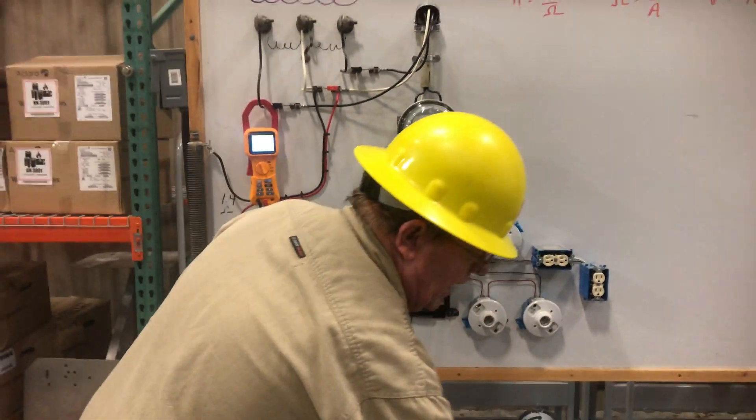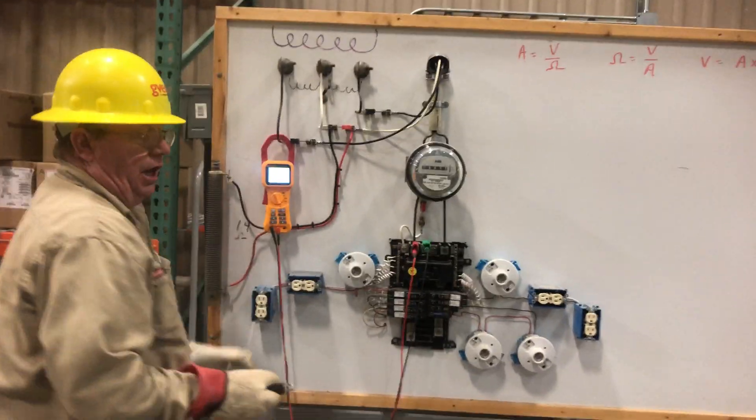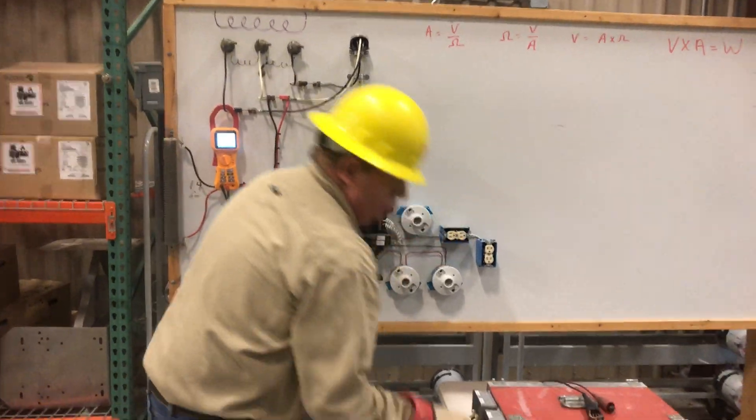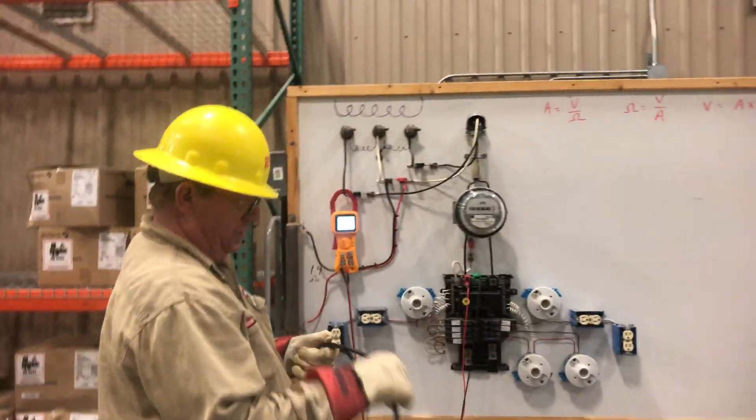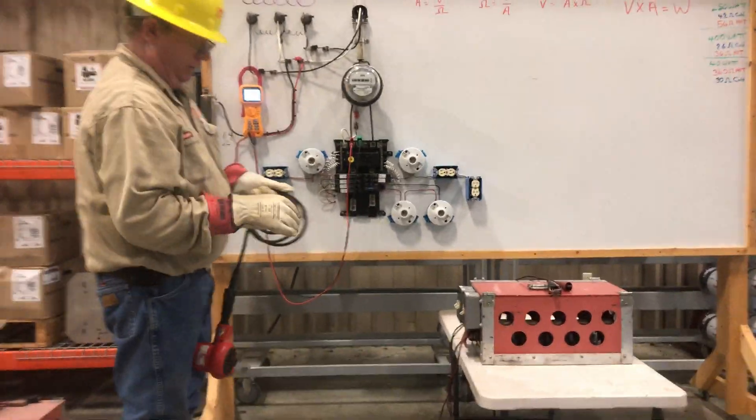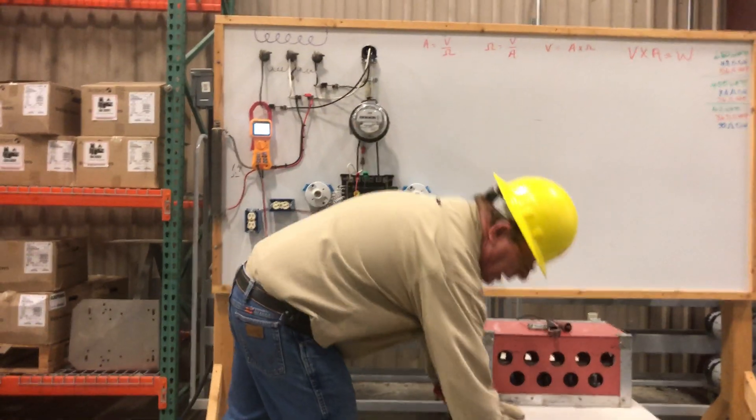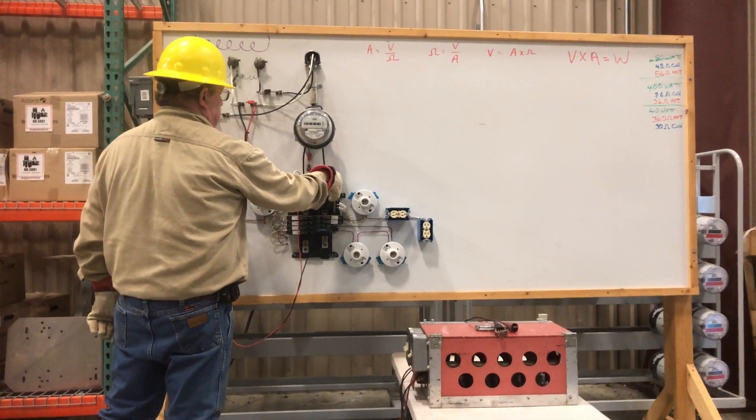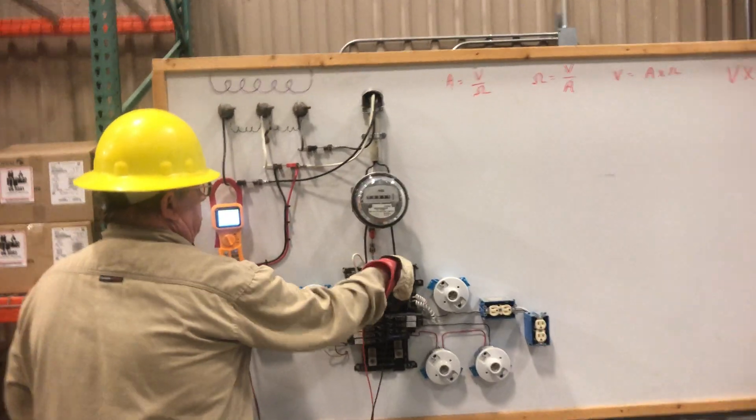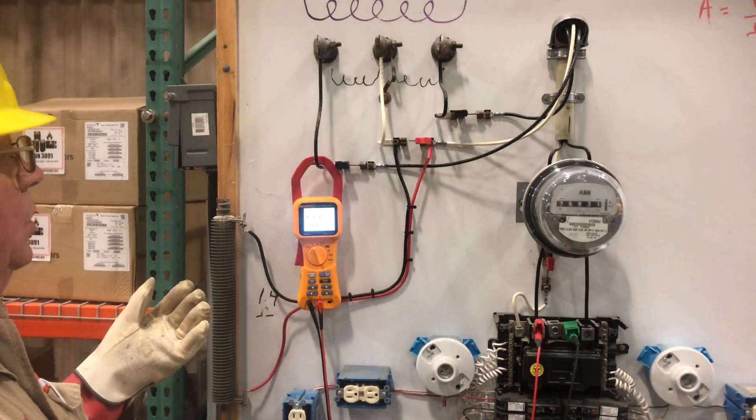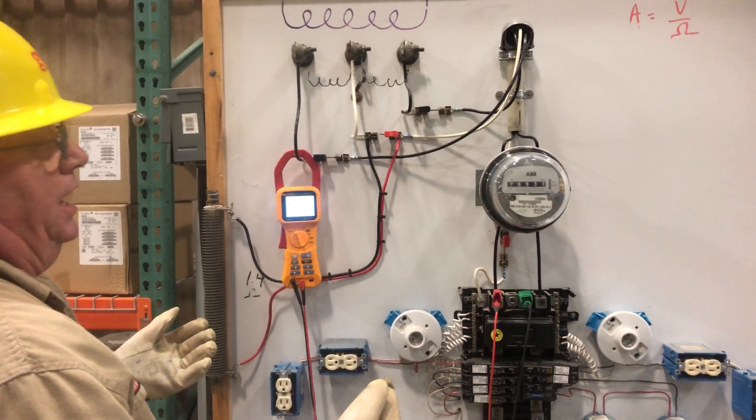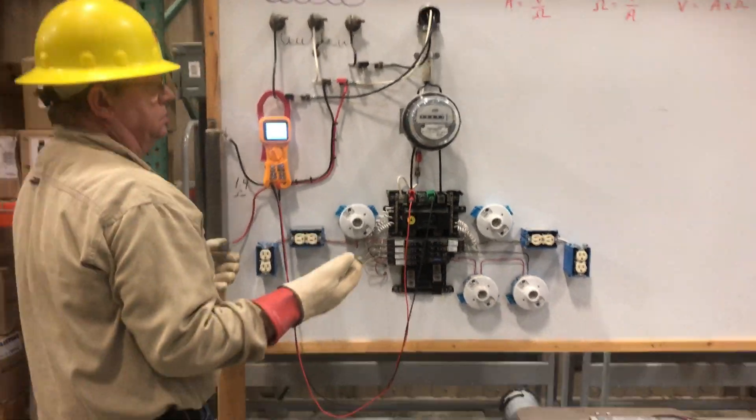So if you went to Ms. Smith's house and she wasn't there to add a load that could create a neutral imbalance, you'd never see that voltage difference between the loaded leg and the unloaded leg. So let's pretend that Ms. Smith is not home. We have 242 and 121. We have not even used an amp meter yet to determine that there's no load. Nobody's home.